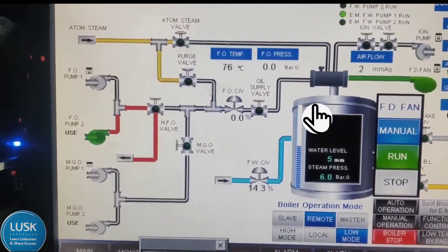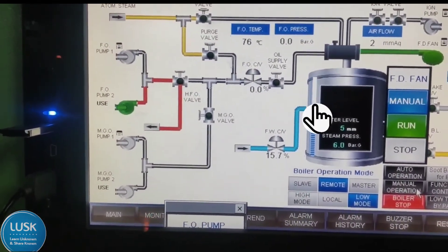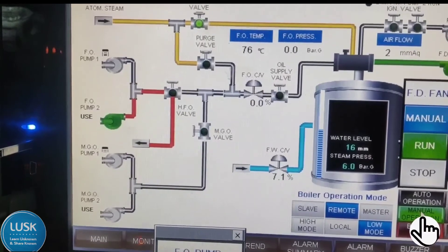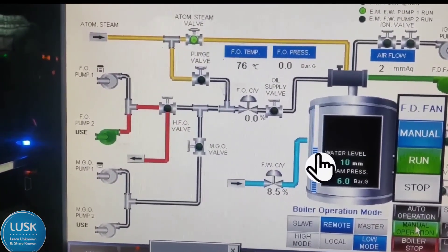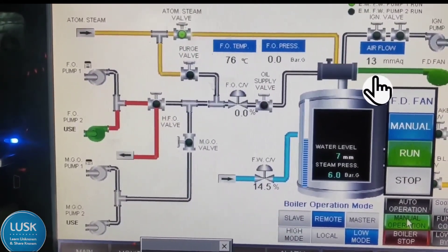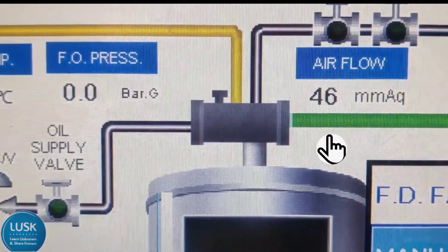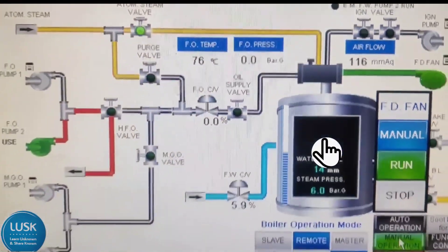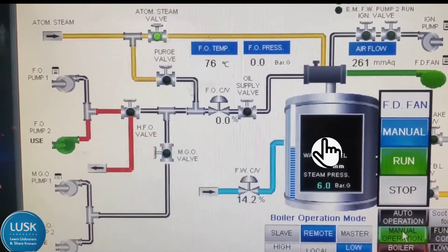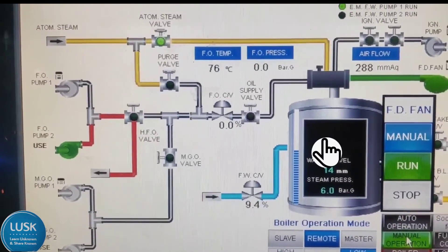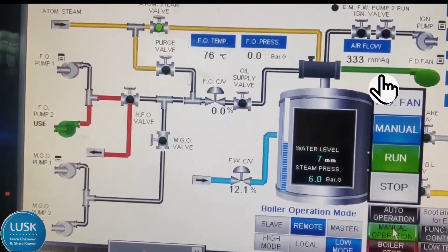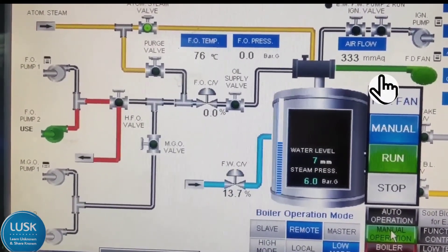When more amount of air is required, the flap will open slowly and more air will go inside the boiler for firing. Now we press manual operation — the boiler is going to start the sequence. You can see the FD fan flap is opening slowly; it was 2mm and now it is going to the maximum, around 300 to 330, which is full open. It will vary according to boiler brand. The purging period will be happening for approximately 1 minute.